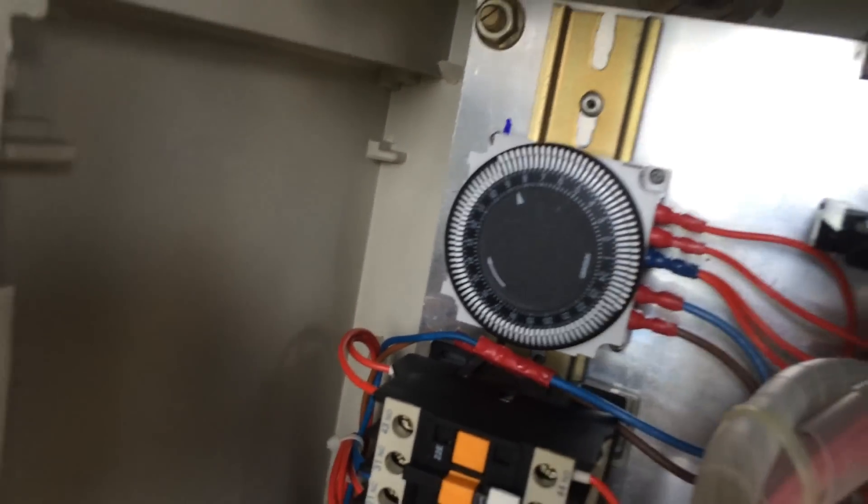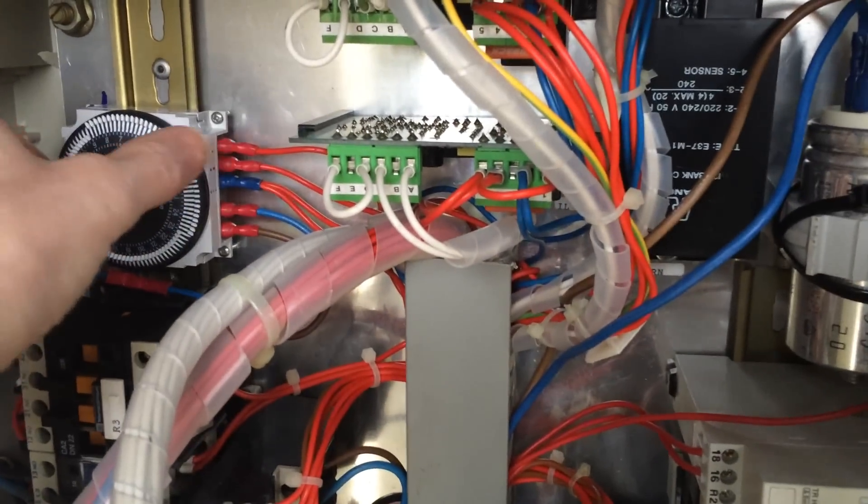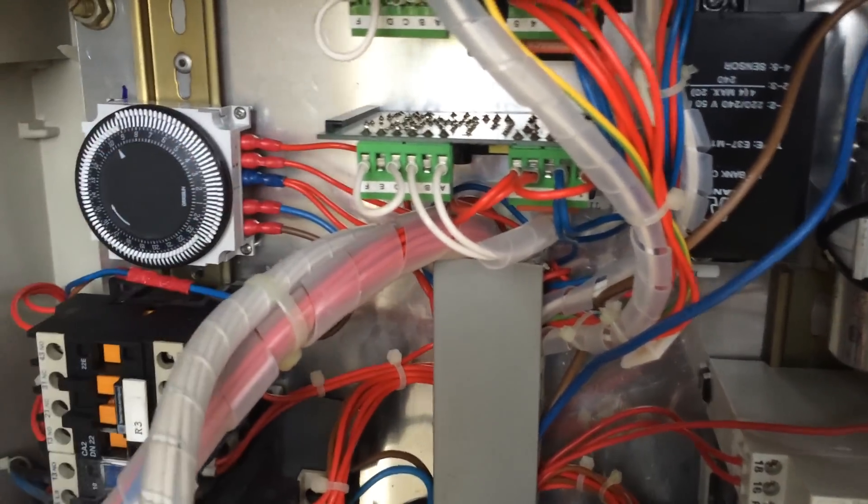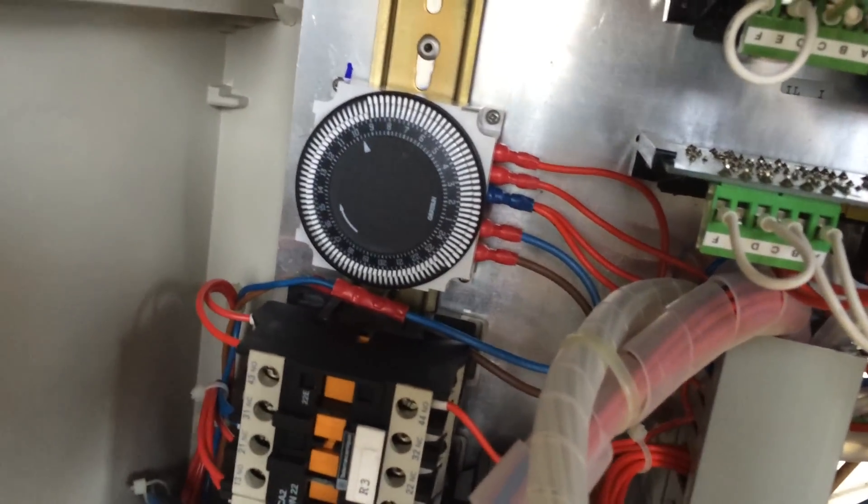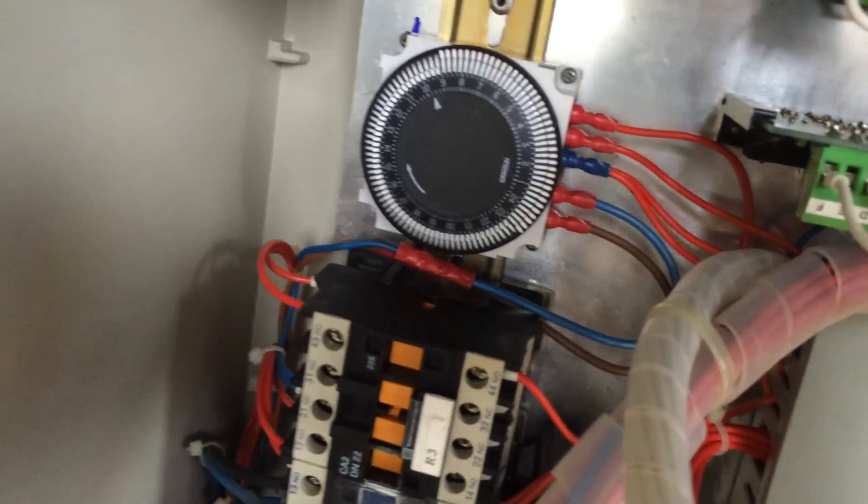We're just checking the operation now. It's set to come on at 11 o'clock at night, and it should turn off at 9 o'clock in the morning, which it does. Then once it goes on to that time, it switches over to the low ice probe sensor, I think.